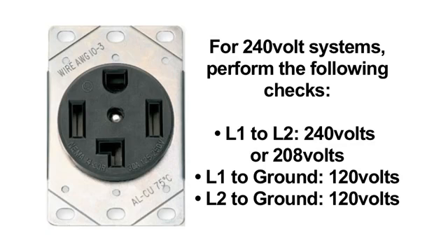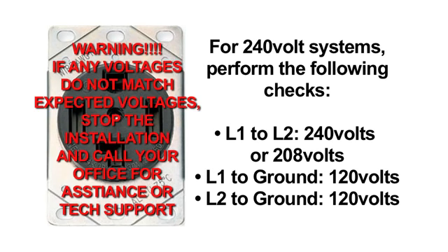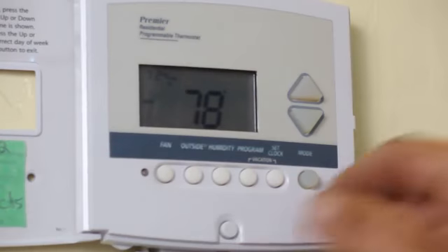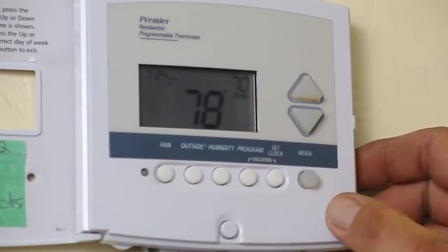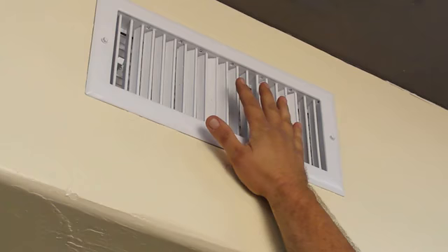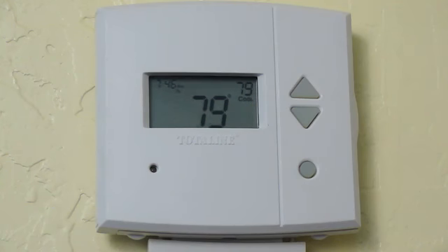For 240 volt systems, perform the following checks: L1 to L2, 240 volts or 208 volts. L1 to ground, 120 volts. L2 to ground, 120 volts. If any voltages do not match expected voltages, stop the installation and call your office for assistance or tech support. Next, verify the thermostat controls for the fan are in the on position. After that, confirm the unit operates satisfactorily by changing the set point.